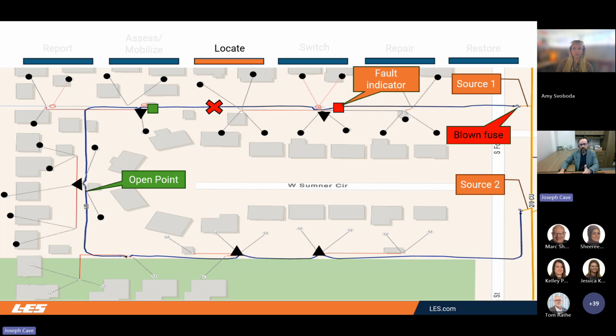The goal is to get out on site and to figure out what the source of the problem is. So the system has anticipated what the problem is, but we don't know exactly why that fuse has blown. So we'll get a troubleshooter out on site, and they'll go around and they'll look at what we call fault indicators that give us an idea of where the fault occurred. So in this instance, the red fault indicator says that the fault was past that point on our system. And the green fault indicator on the next transformer says that it did not see that fault, or the fault is before that point in the system.